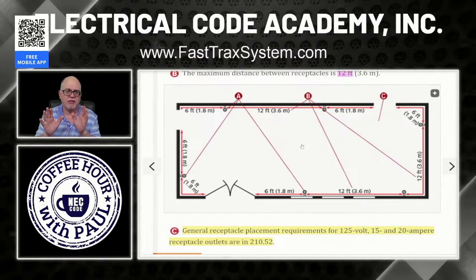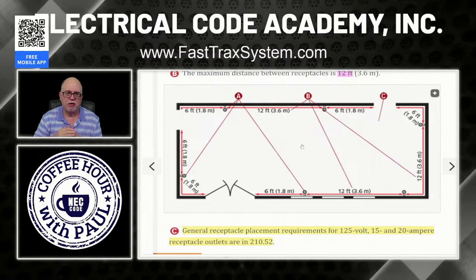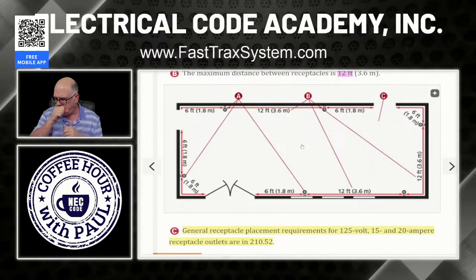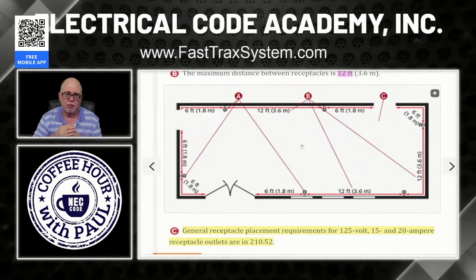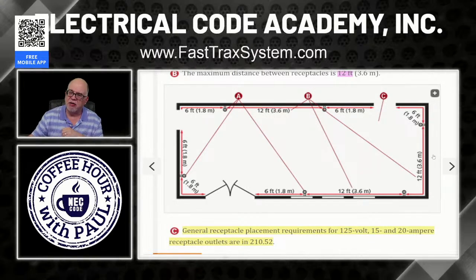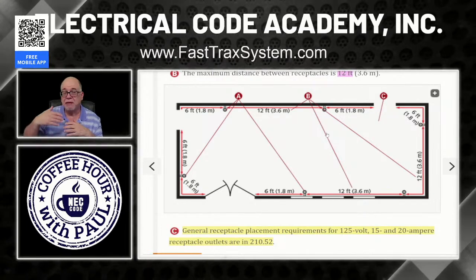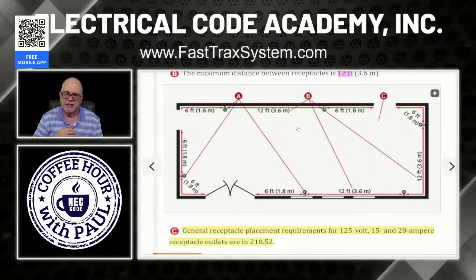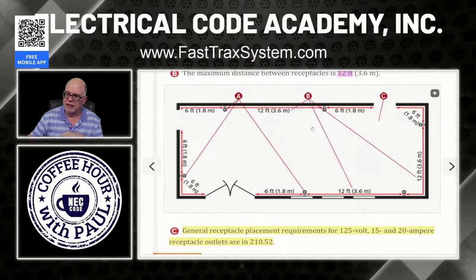But I'll give you another example. A receptacle in a kitchen that's serving the countertop. If I have a receptacle up in the cabinet for some reason, that is not going to replace the ones that are still required for your spacing around the kitchen and the spacing on the countertop, which we haven't covered yet, which is called the 2 foot, 4 foot rule. But we haven't really gotten into that spacing yet. The point is, I might have a receptacle in a cabinet, but that's not going to meet the spacing rules. So they can be there, but you're going to have one out on the wall available to meet the spacing rule in 210.52, okay?